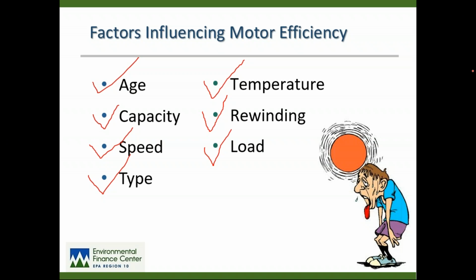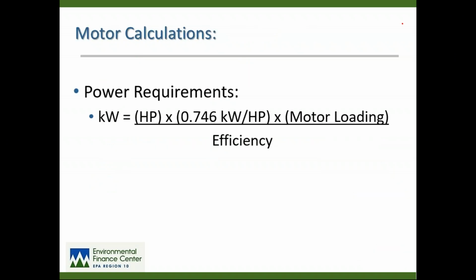Again, sometimes when we do an energy audit, we see motors that are out there that are way underloaded because they were designed for conditions 20 or 30 years from now. Any motor that is loaded with less than half of its operating capacity in terms of horsepower is throwing a lot of money down the drain in terms of energy use. And you may have a motor like that in your system.